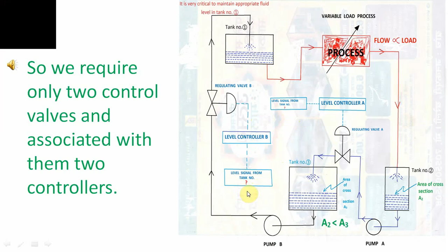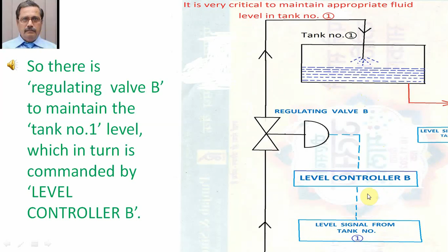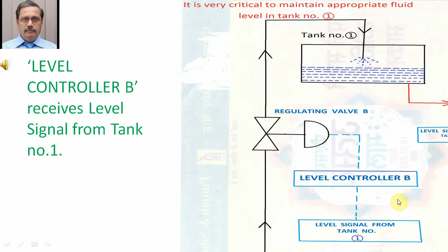Answer to the question number 1. The first choice shall be tank number 1 because it has been mentioned that it is very critical to maintain appropriate liquid level in tank number 1. So there is regulating valve B to maintain the tank number 1 level, which in turn is commanded by level controller B. Level controller B receives level signal from tank number 1.